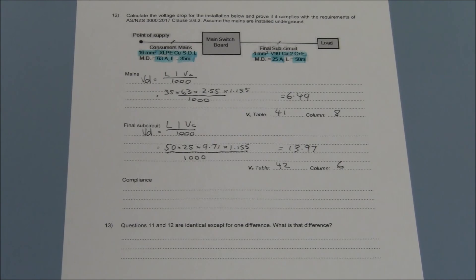AS3000 states that voltage drop shall be such that it does not exceed 5% between a point of supply and any other point within the electrical installation. In a single phase installation that value is no greater than 11.5 volts.